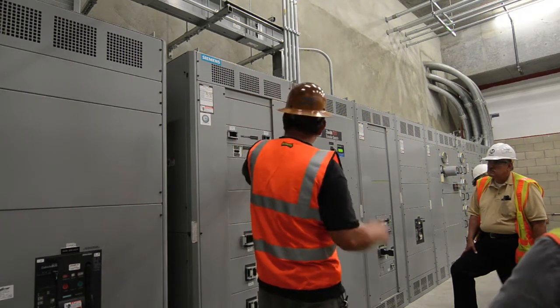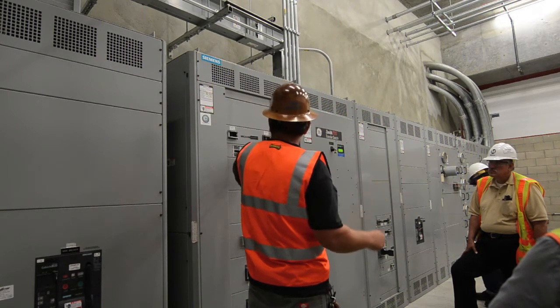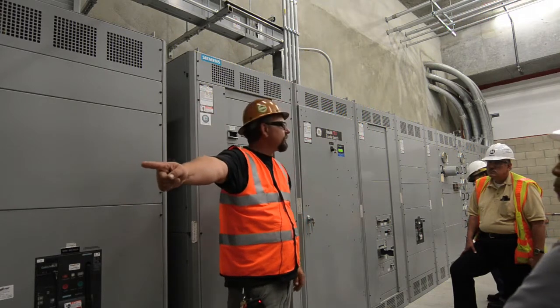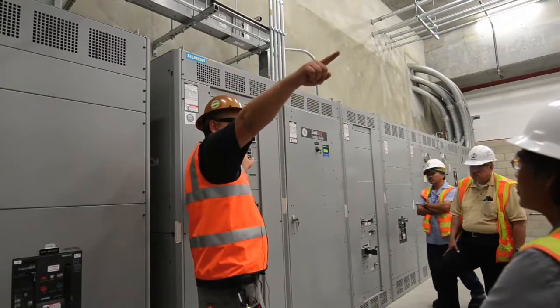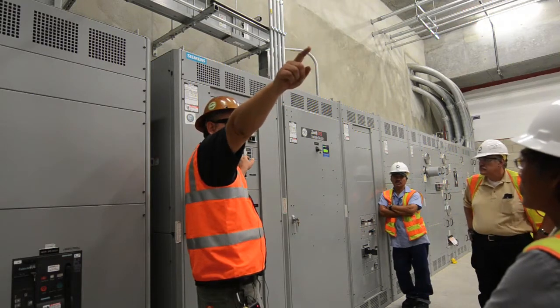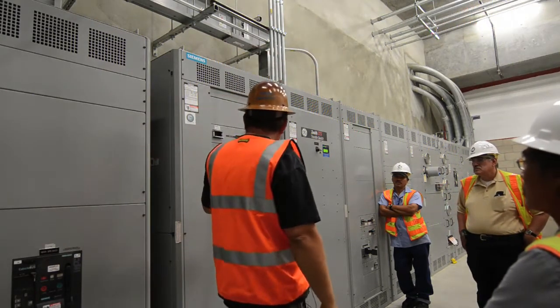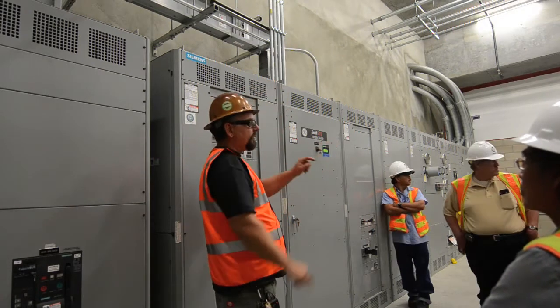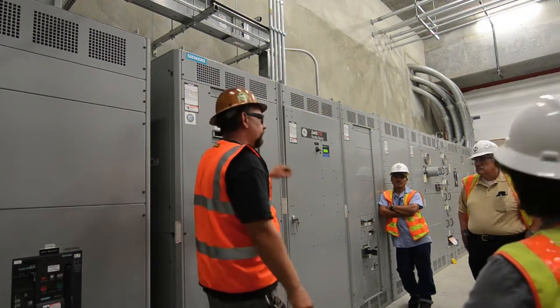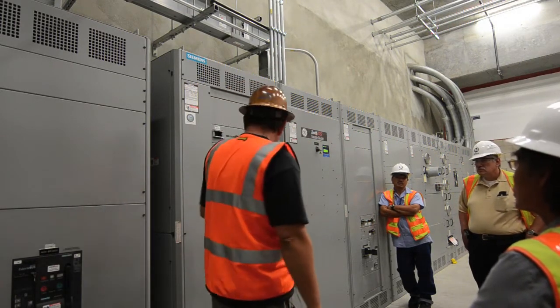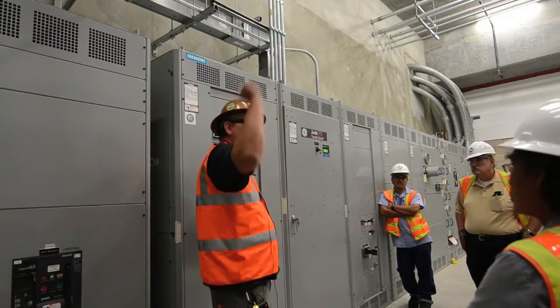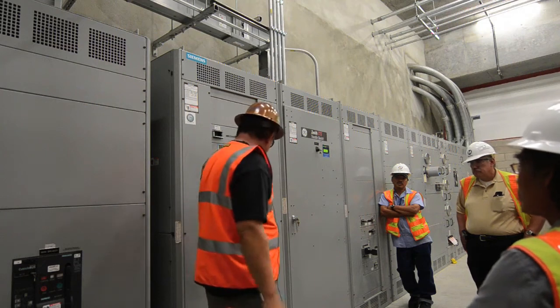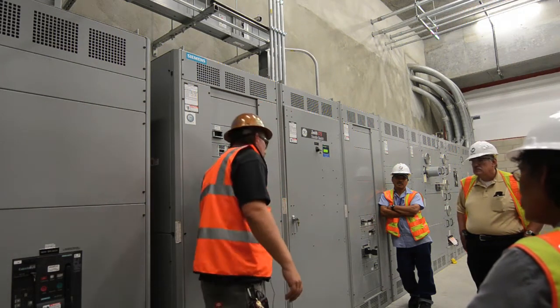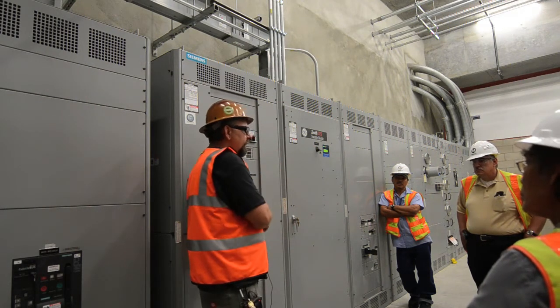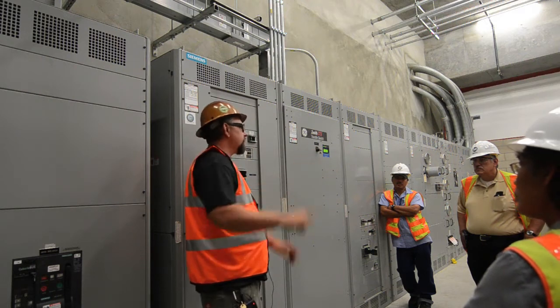This switchboard controls elevator 3, which is the elevator on the west side. Controls panel EH2, which is right there, which is your emergency lighting on both levels. It controls your wastewater pump and your stormwater pump, which I'll point out to you as we're walking out. They're on the south wall, those two ejector controllers. It controls the two VFDs, which are those two big white guys for the two large exhaust fans. So during an emergency, those are going to run. It controls panel EH1, which is in the retail building. I'll show you the other side of that. I owe you a label here. And then you have two spare breakers, and there's two empty 4-inch conduits that go from here to the other side of the building. I'll show you where the other end of those are.